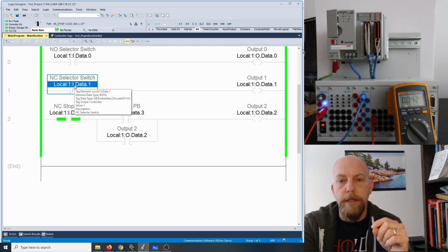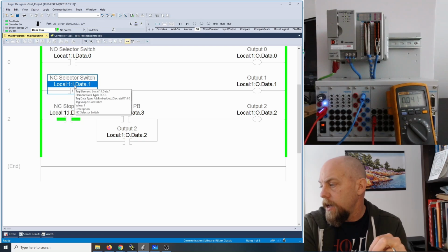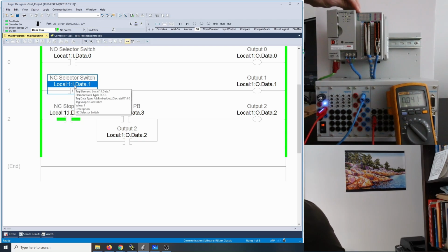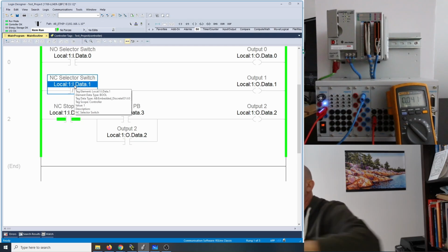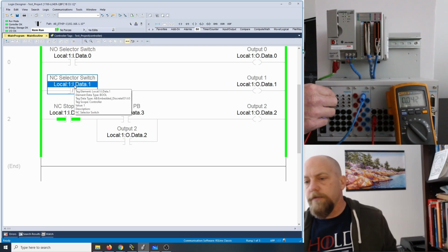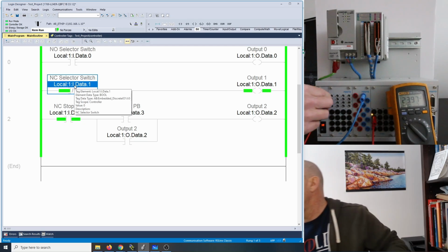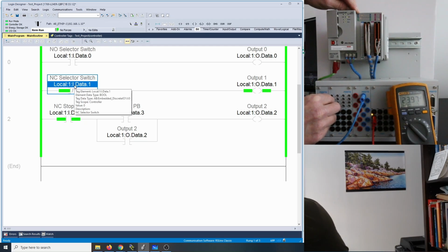So there's clearly voltage being applied to input number 1. You might just be able to see that this LED here for number 1 is on with that voltage. And if I change the state of that, then it's now a 0. I don't know if you can make out this tiny LED right there. So there's voltage applied to the terminal. There's no voltage applied to the terminal.